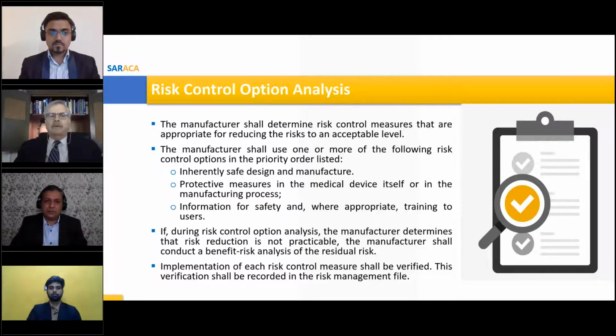If you determine in a risk control analysis that the risk is not practical to reduce, the manufacturer needs to conduct the benefit risk analysis of the residual risk. And if you can't do that, you need to consider going back. If the residual risk overwhelms the benefit, you may need to go back and look at the design of your process or your manufacturing process or the design of the device and consider modification. Each risk control measure needs to be verified, and then the verification shall be recorded in the risk management file, which is then reviewed as part of your verification before you release it into the market.